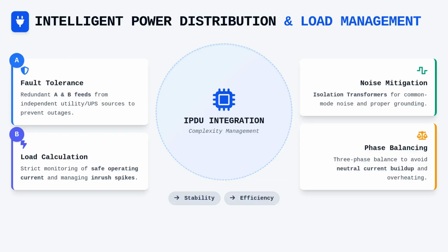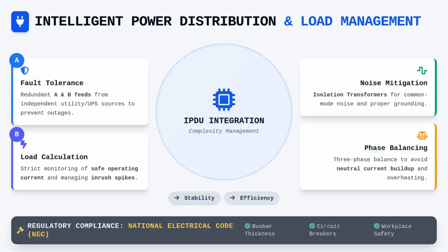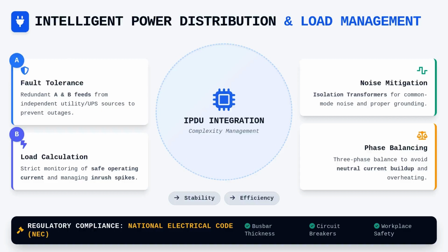A well-designed power infrastructure acknowledges that phase loading must be balanced across the three-phase distribution. Failure to perform this balancing leads to neutral current buildup, which can cause significant overheating in cables and transformers regardless of the total power being consumed. Every design choice, from the thickness of a bus bar to the selection of branch circuit breakers, must align with strict national electrical code regulations regarding service conditions and workplace safety.